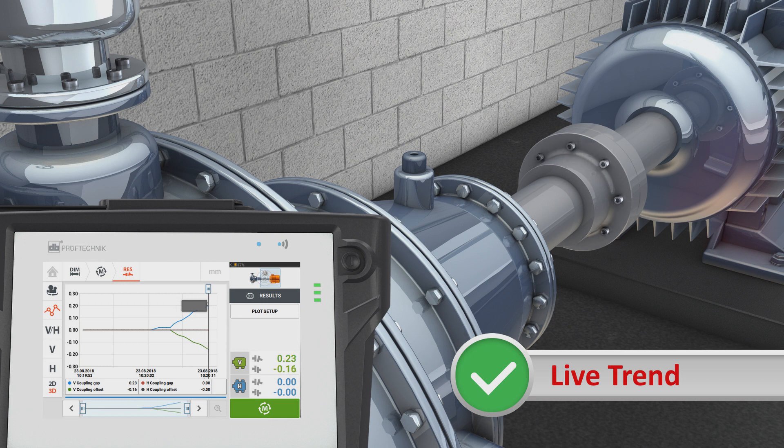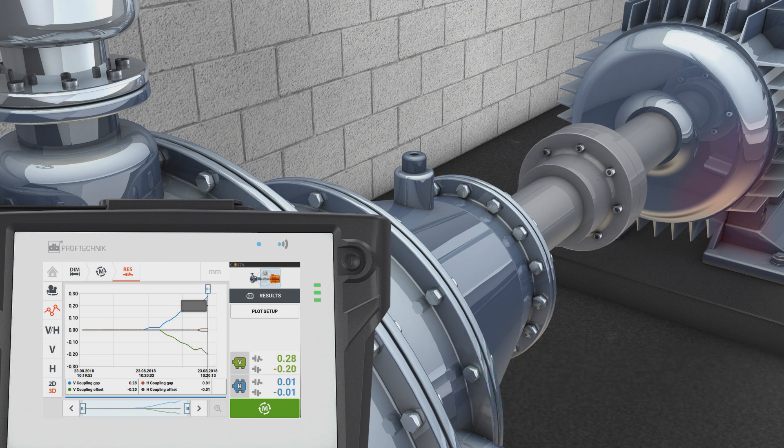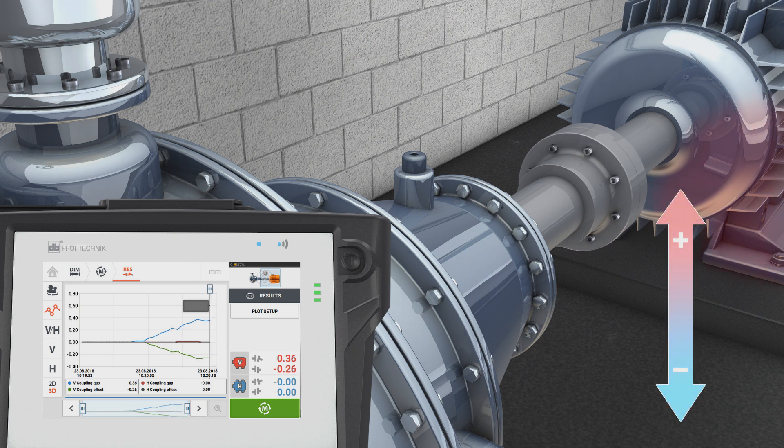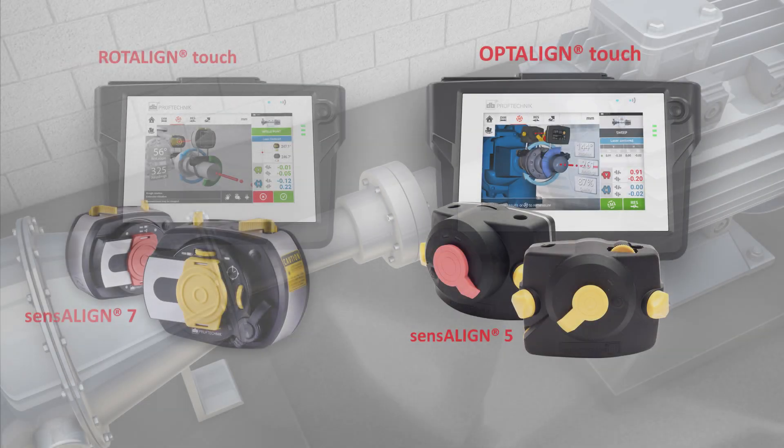Based on the X and Y split detection areas, the SensALIGN laser sensor technology is able to record the thermal growth of the machine while it is running up. The SensALIGN measurement technology is available with ROTALIGN touch and OPTALIGN touch.